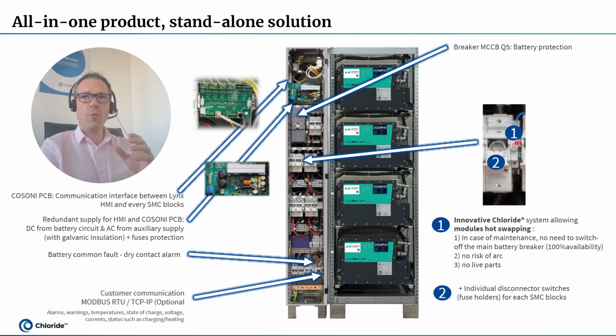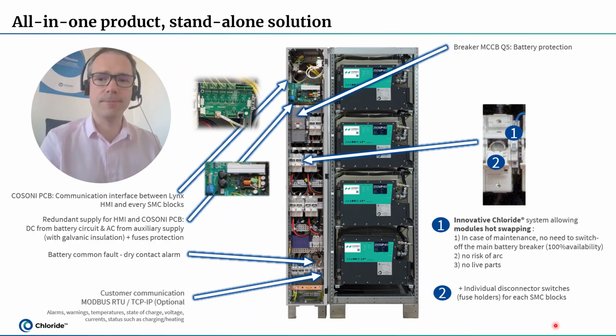So as soon as we open this small switch, automatically the relay inside the battery will be opened, and then we can open the fuse holder and remove the power connector there with no risk of arc. So again, if one day you want to replace this block, there is no need to open the battery breaker thanks to these systems. And we have this system, fuse holder plus these small relays, one for every block. That's the reason why you can see 1, 2, 3, 4 systems like this located there.